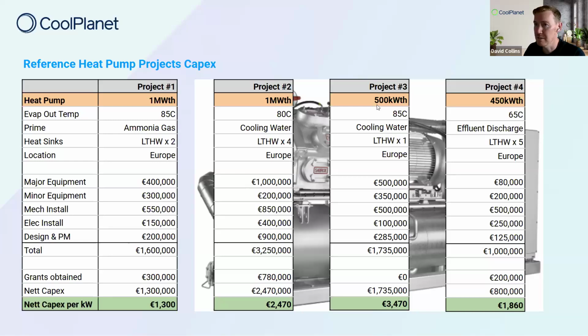The next project here is a 0.5 meg heat pump producing 85 C water. Again, the source of the prime was cooling water from the site. This was an edible oil site. The only heat sink here was just a single heat sink to preheat incoming air for part of their process. It's a dryer application in their process. Again, previously the site was using steam to provide that source of heating for the air heating, and now they're preheating that air with LTHW coming from the heat pump. Still quite a complex installation, and it averaged out about 3,500 euros per kilowatt installed.